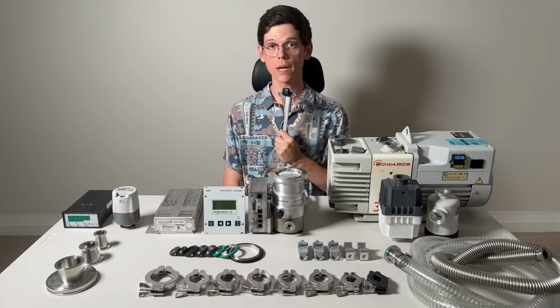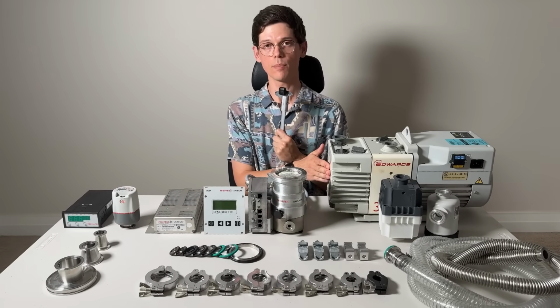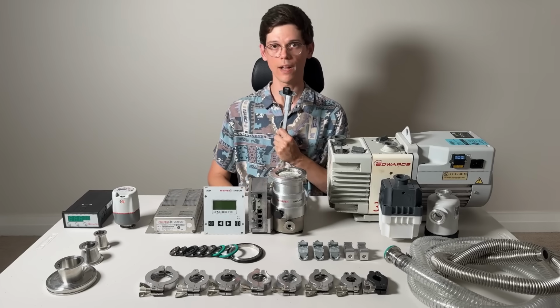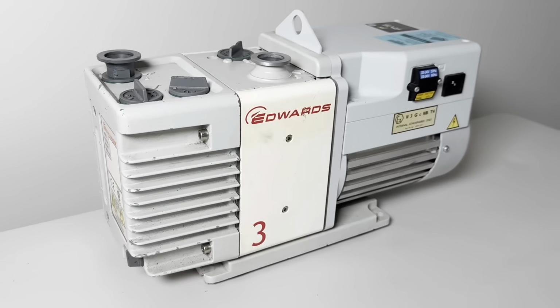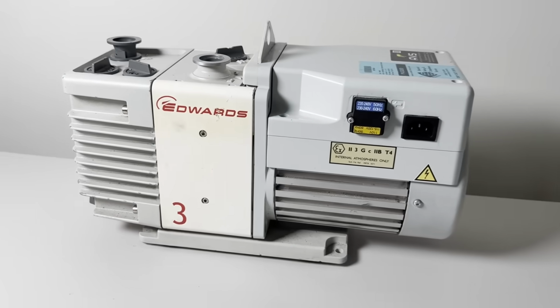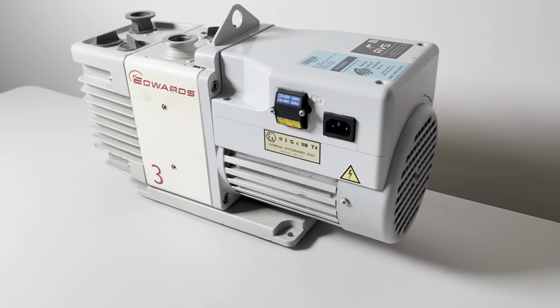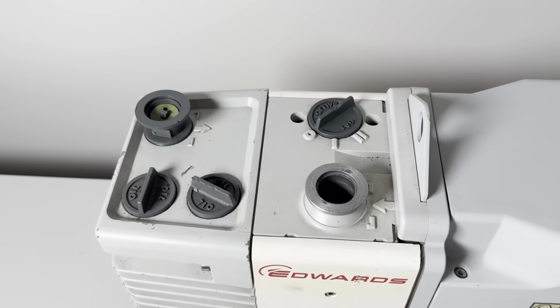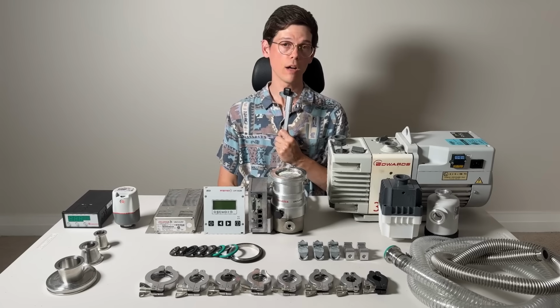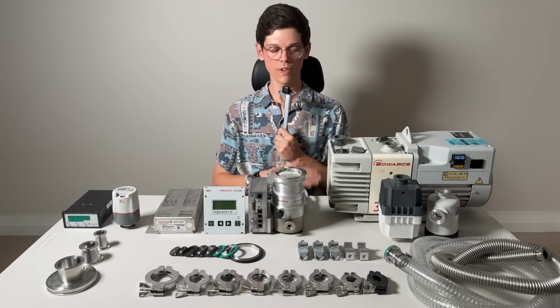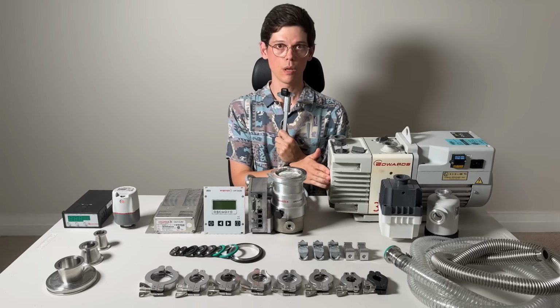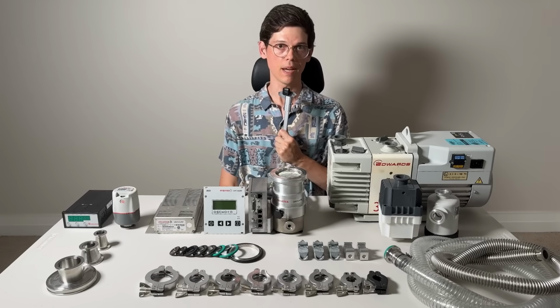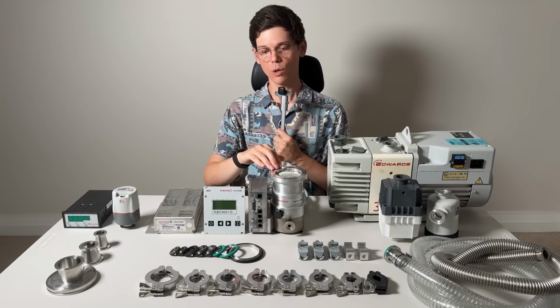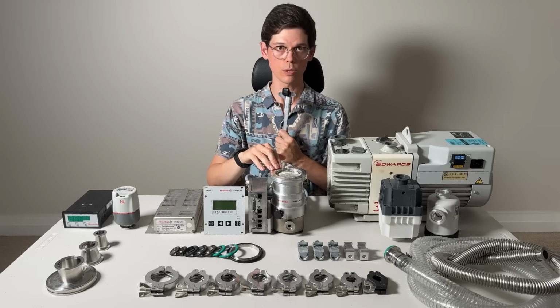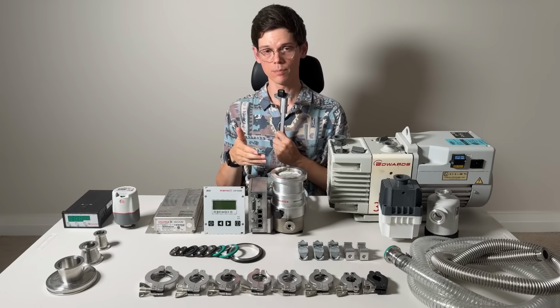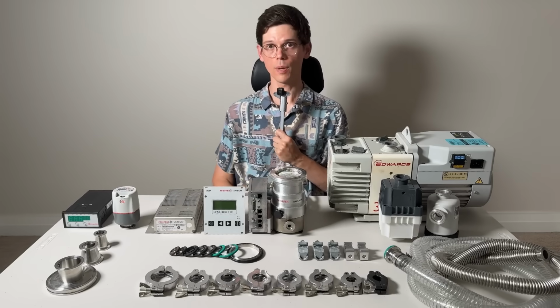The second thing to note is that the rotary vane pump has something called an anti-suckback valve. And what this does is if the pump stops running for any reason, like if it breaks or there's a power outage, and air at atmospheric pressure tries to rush into the vacuum, the valve closes and stops it. This prevents the oil that's inside the pump from being sucked into the chamber and contaminating everything, and it prevents the turbo from seeing a huge pressure spike, which, as we just discussed, can damage it. So it's a super useful feature for the pump to have.